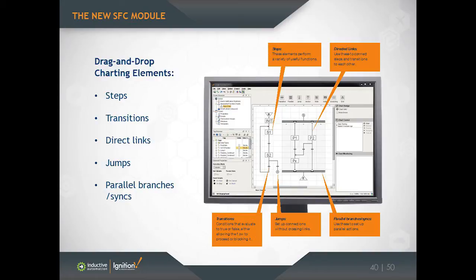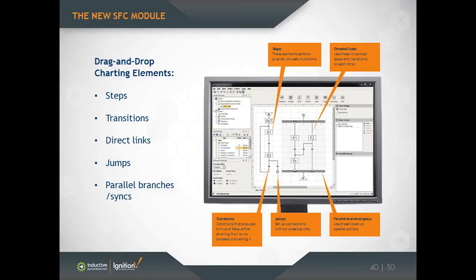And then steps are connected to each other, and they're also connected to the chart using transitions. So a transition is this short horizontal bar that you see here in that screenshot. A transition represents a condition, and the condition is either true or false, and whether it's true or false determines whether or not the chart can move past that transition or not. Pretty simple idea.